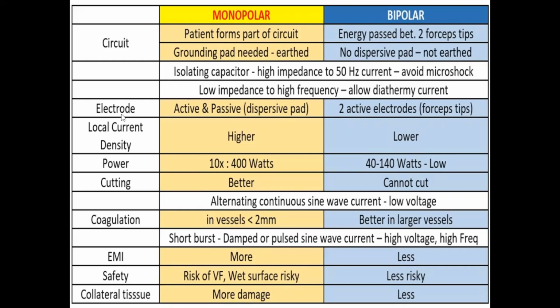Okay. Next, electrode. In monopolar you have an active electrode and a passive electrode, which is the dispersive pad. There's only one. The active is the pen-like end that touches the tissue. Your passive electrode is your pad. But in bipolar, both the forceps tips act as active electrodes. That's why current only passes between these two. Local current density is higher in monopolar because it goes through the tissues and is dispersed. But in bipolar, it stays between the two electrodes, so the current density is lower.